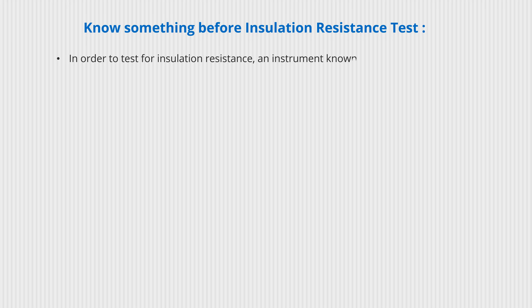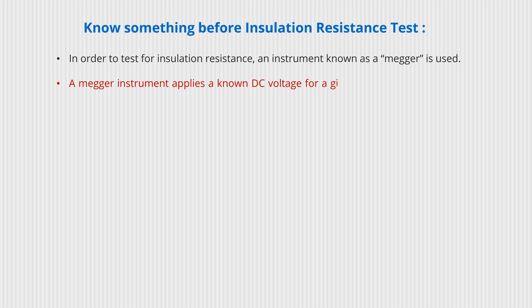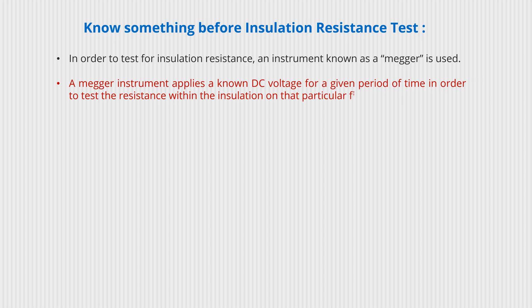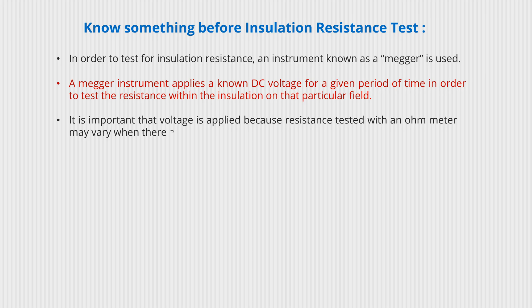Before performing an insulation resistance test, you should know that an instrument known as a megger is used. A megger instrument applies a known DC voltage for a given period of time to test the resistance within the insulation on that particular field. It is important that voltage is applied because resistance tested with an ohmmeter may vary when there is no potential difference present.